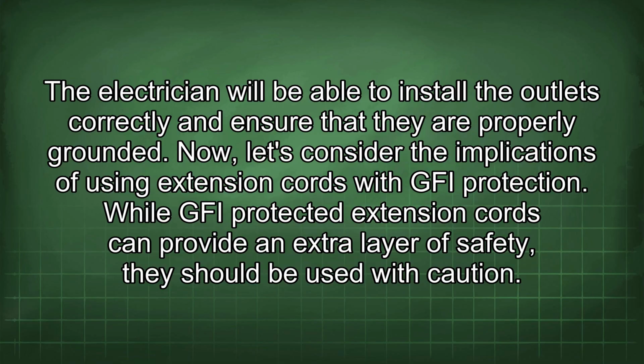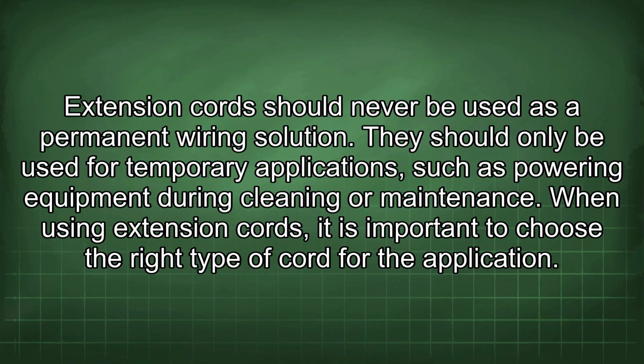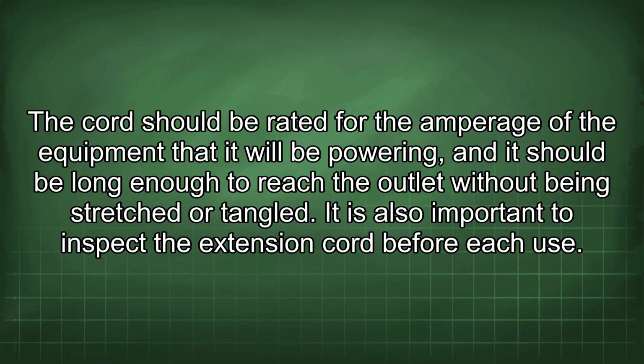Now, let's consider the implications of using extension cords with GFI protection. While GFI protected extension cords can provide an extra layer of safety, they should be used with caution. Extension cords should never be used as a permanent wiring solution. They should only be used for temporary applications, such as powering equipment during cleaning or maintenance. When using extension cords, it is important to choose the right type of cord for the application. The cord should be rated for the amperage of the equipment that it will be powering, and it should be long enough to reach the outlet without being stretched or tangled.